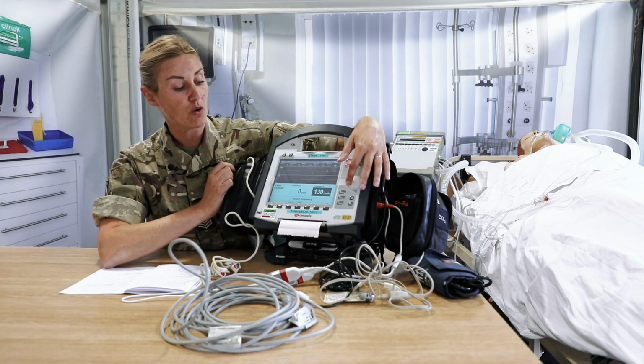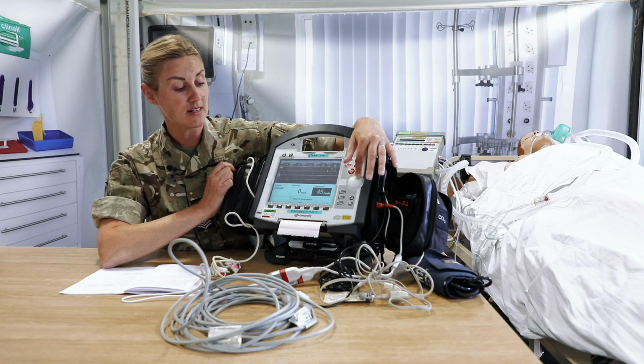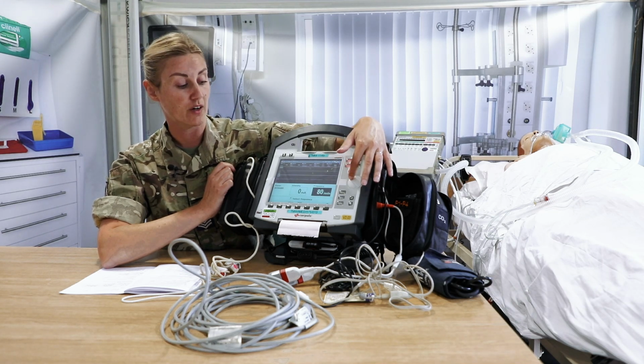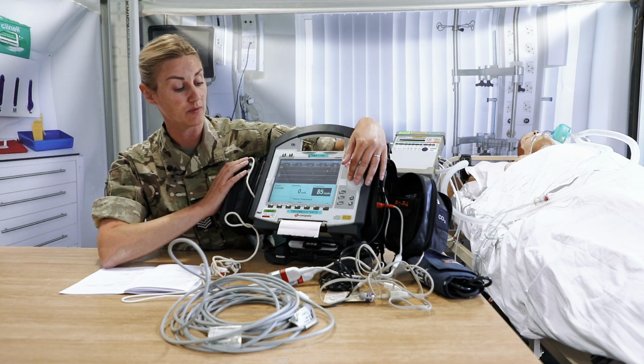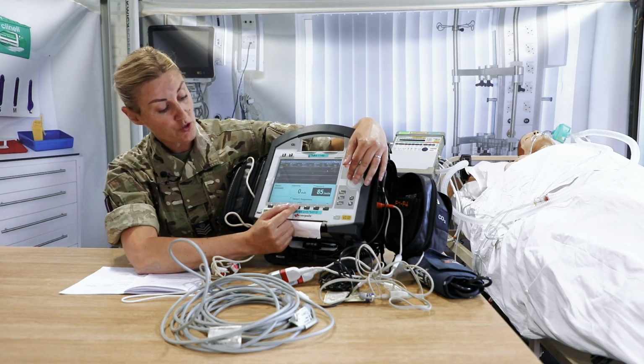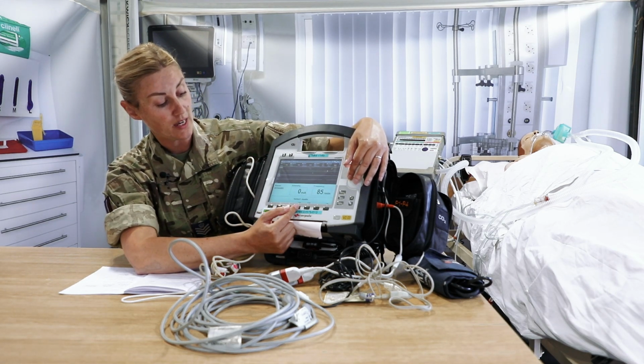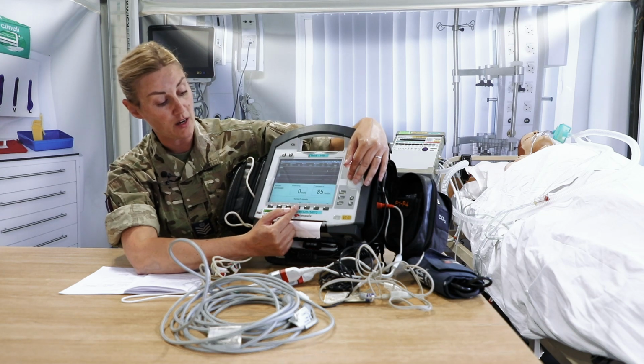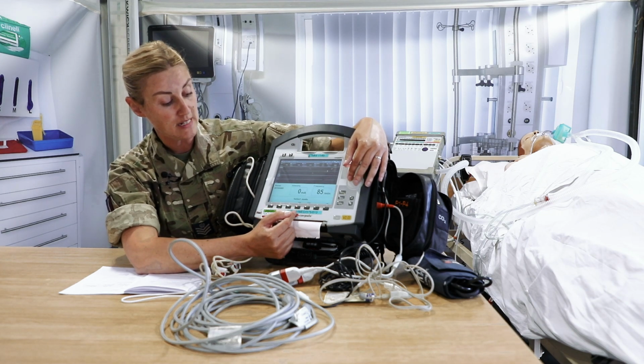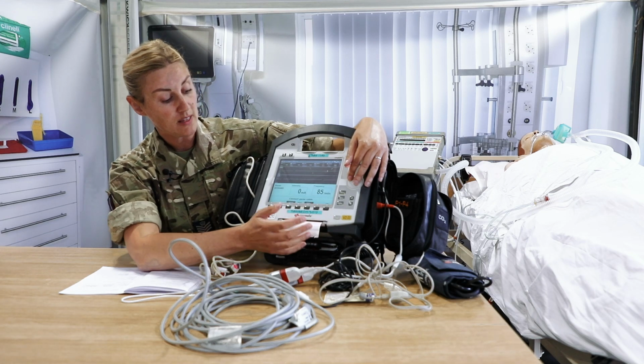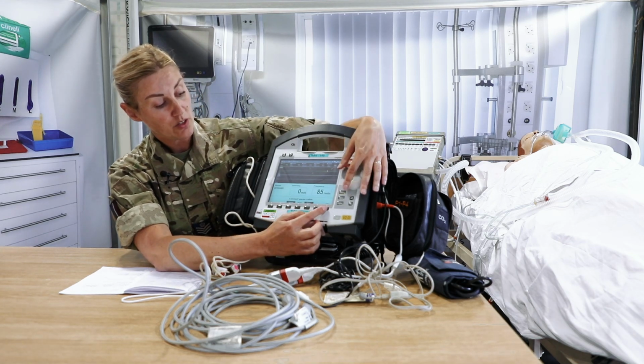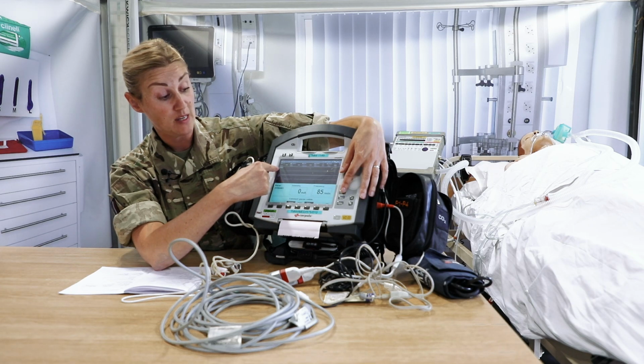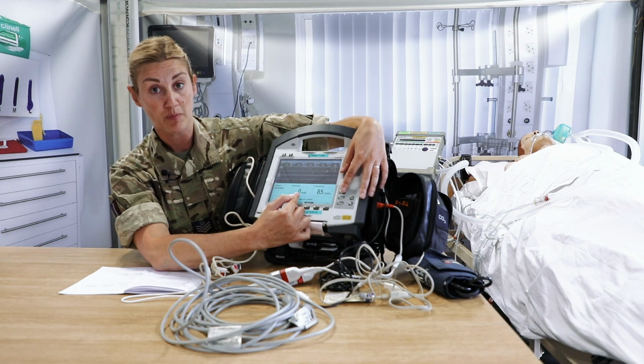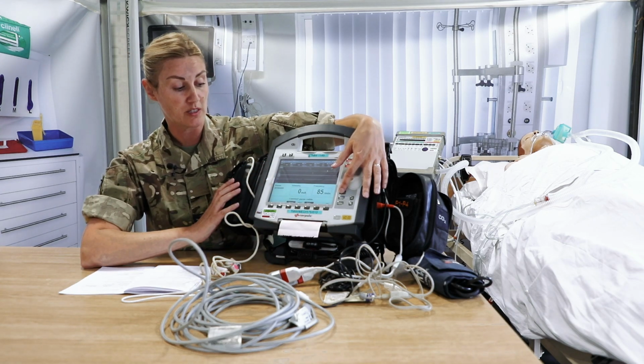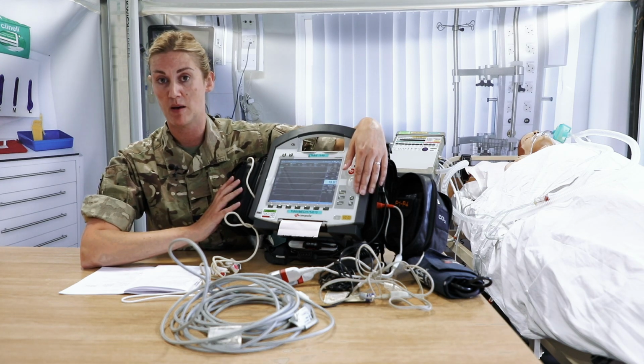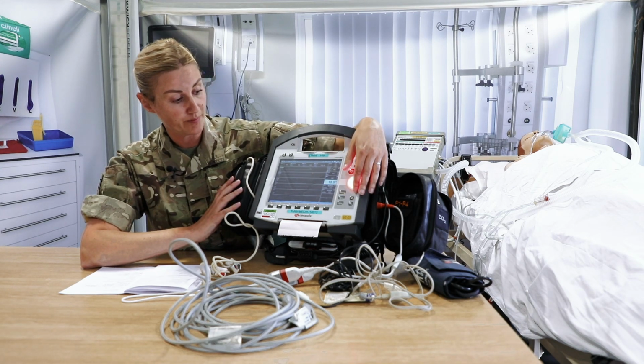So this should go all the way up to 150 again and down to 30. So just confirm that and just settle somewhere in the middle. You can change modes, so just check that you've got some modes here. So you've got a demand, a fixed and an overdrive mode if you need it. But otherwise, that's all we're going to check in the pacemaker. So if STIM is not there and there's no milliamperage selected in the intensity, we can just press the monitor button to disarm that pacer and go back into our main screen.